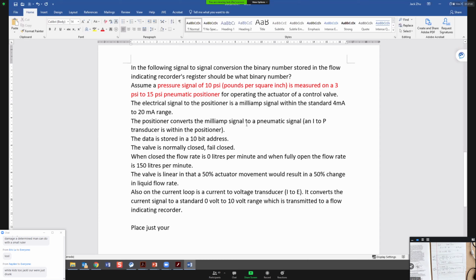The positioner converts the milliamp signal to a pneumatic signal. The data storage is 10 bit, so that's also something we care about. The valve is normally closed, fail to open. When closed, it's 0 liters per minute, fully open is 150 liters per minute. The valve is linear, blah blah. Also on the current loop, current to voltage transducer converts the current signal to standard, and the transmitter follows to the indicating recorder. So from here we know 3 psi causes it to close, and at 15 psi it causes it to open.